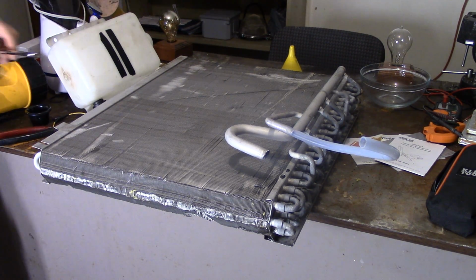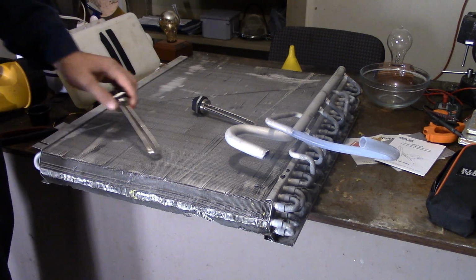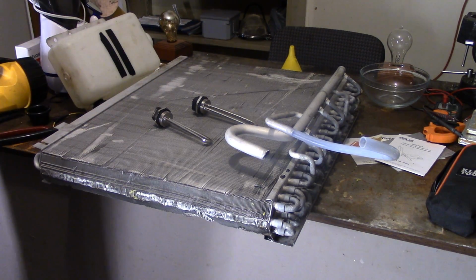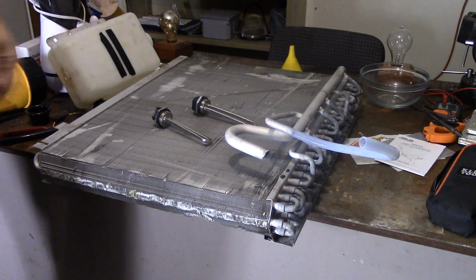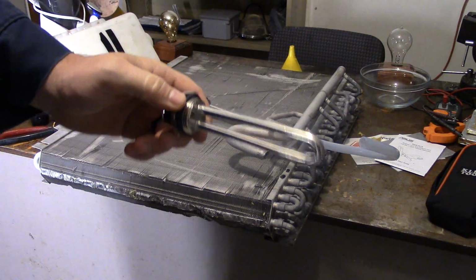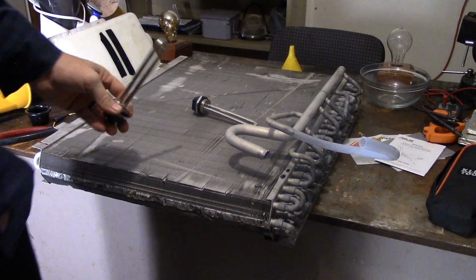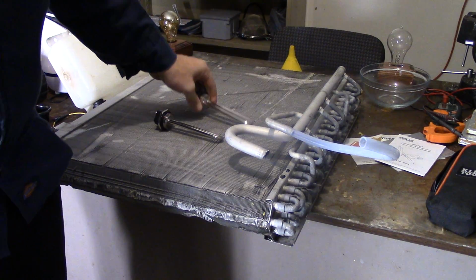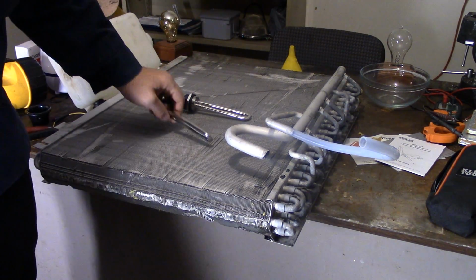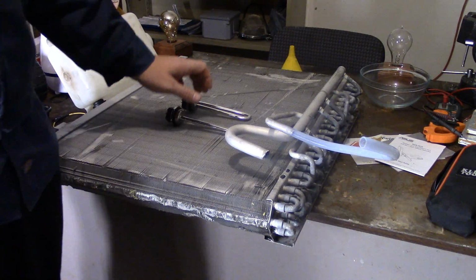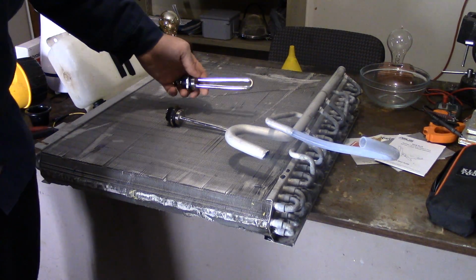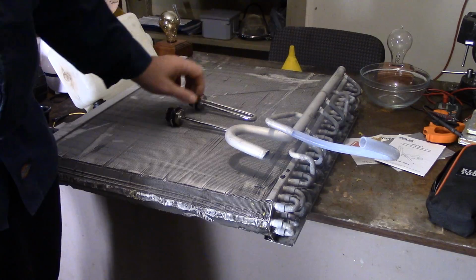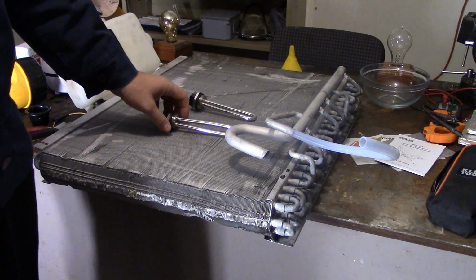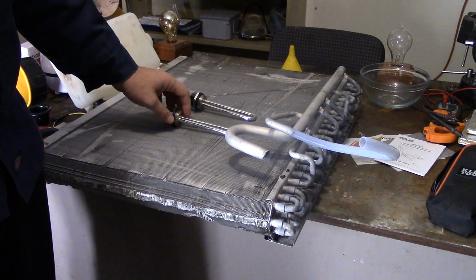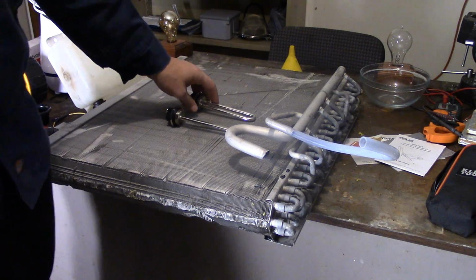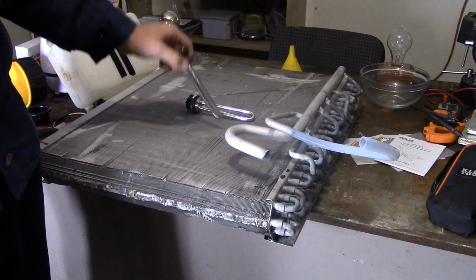Now I could use these heaters on a hot water tank. These heaters insert into a hot water tank and heat up 600 watts each, so that's 1200 watts. Now you're going to be screaming at the wall saying, oh my gosh Philip, you can't do that because a hot water heater requires about 4,500 to 5,000 watts just to run, and it runs off 240 volts.